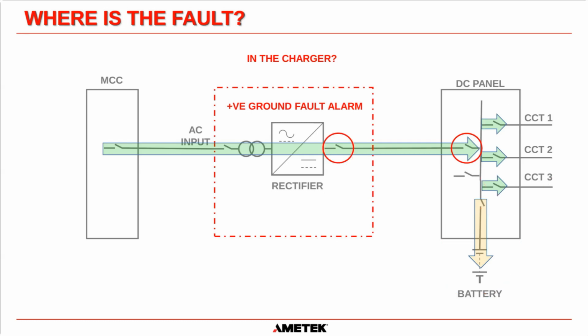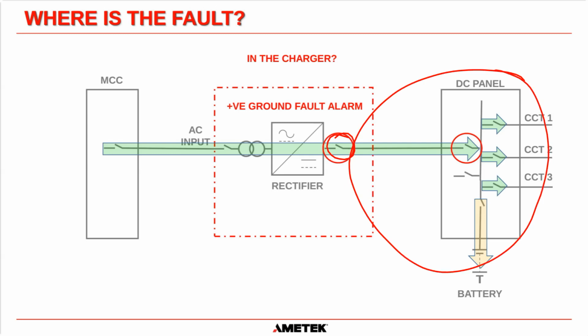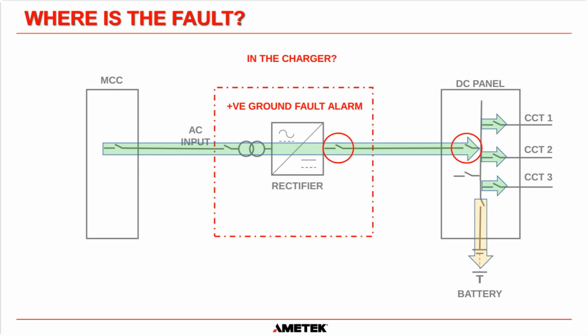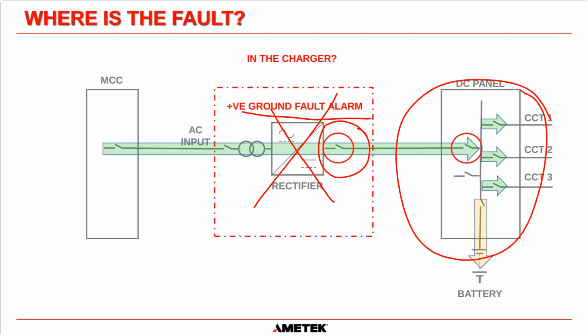But if you open this breaker here and disconnect all of this from the charger, then basically we can say, okay, if we open this breaker and the alarm on the charger remains on, the positive ground fault alarm stays on, we know that the fault is in the charger, okay? If we open this breaker here and the fault goes off, we now know it's not in the charger. It is somewhere either in the battery, the DC panel, or the load circuits. So in one step, we have confirmed one block is either yes, that's the culprit, or is not the culprit, okay?